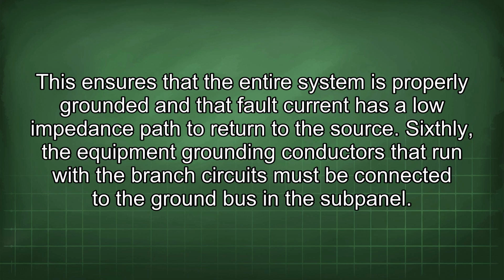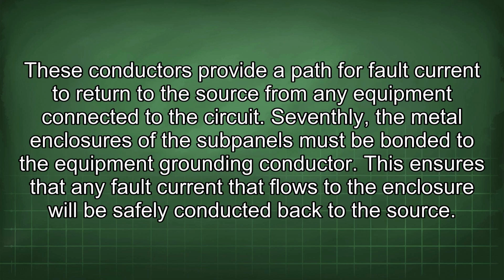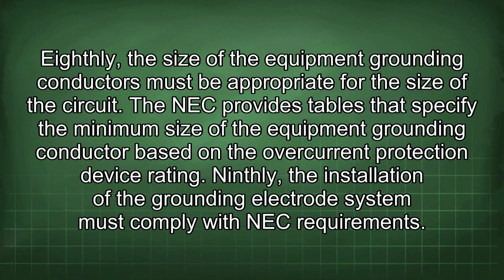Sixthly, the equipment grounding conductors that run with the branch circuits must be connected to the ground bus in the subpanel. These conductors provide a path for fault current to return to the source from any equipment connected to the circuit. Seventhly, the metal enclosures of the subpanels must be bonded to the equipment grounding conductor. This ensures that any fault current that flows to the enclosure will be safely conducted back to the source. Eighthly, the size of the equipment grounding conductors must be appropriate for the size of the circuit. The NEC provides tables that specify the minimum size of the equipment grounding conductor based on the overcurrent protection device rating.